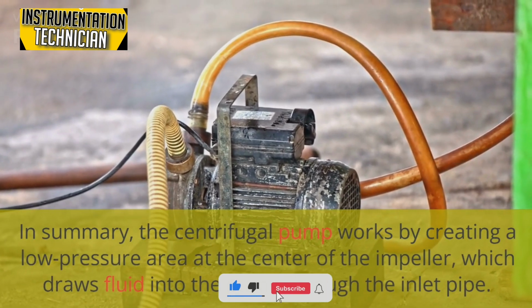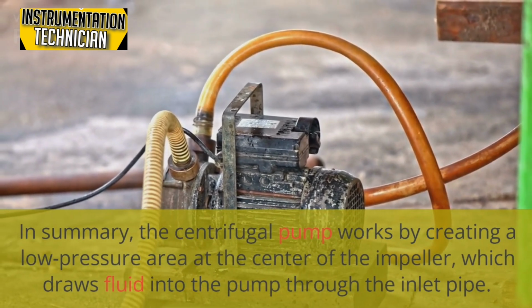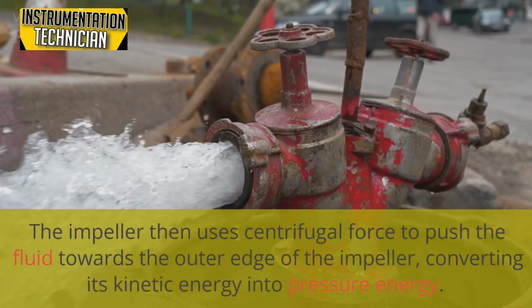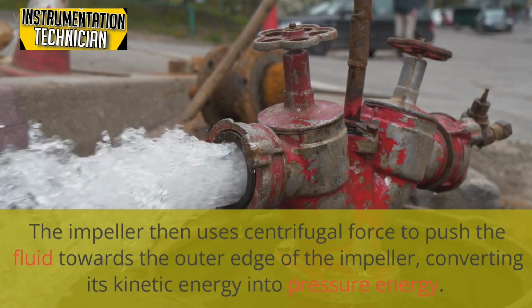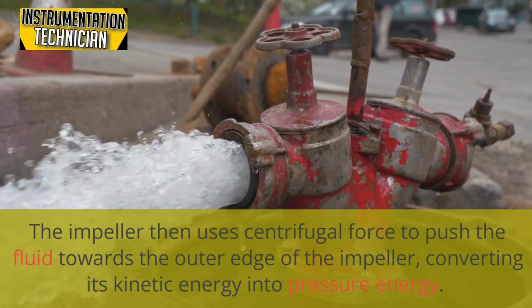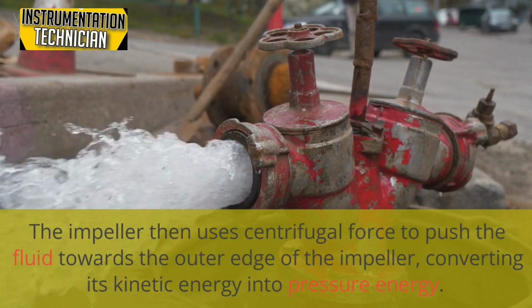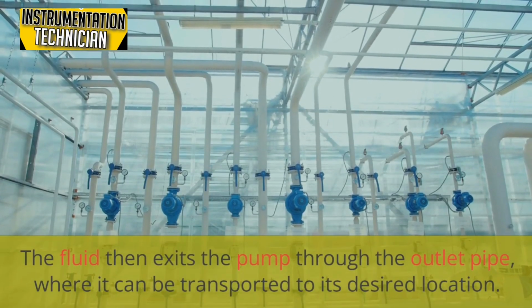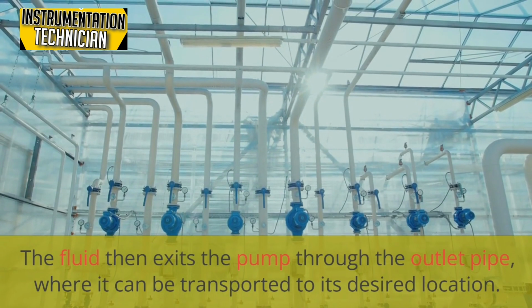In summary, the centrifugal pump works by creating a low-pressure area at the center of the impeller, which draws fluid into the pump through the inlet pipe. The impeller then uses centrifugal force to push the fluid towards the outer edge of the impeller, converting its kinetic energy into pressure energy. The fluid then exits the pump through the outlet pipe, where it can be transported to its desired location.